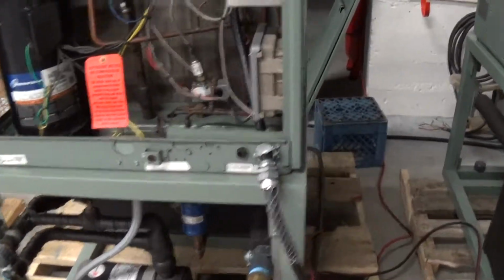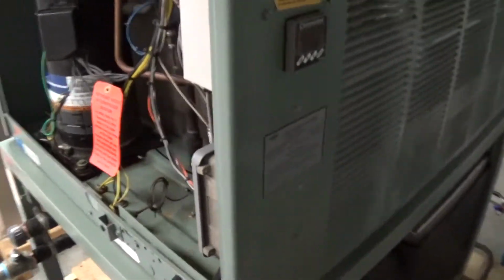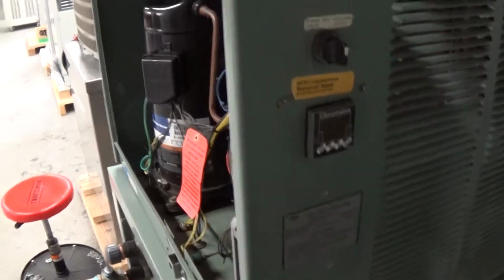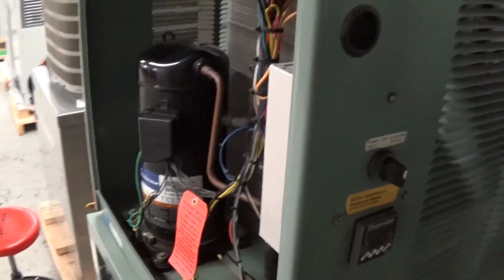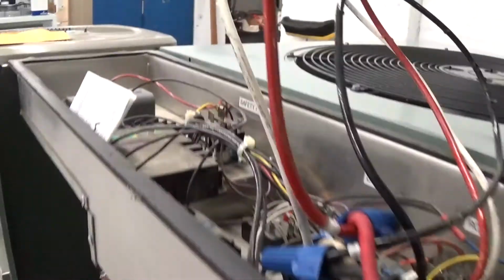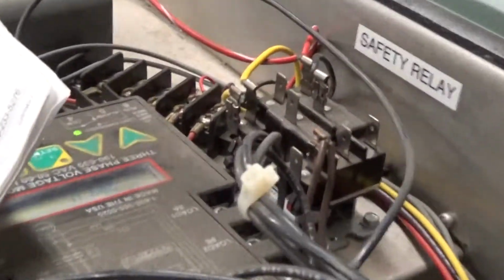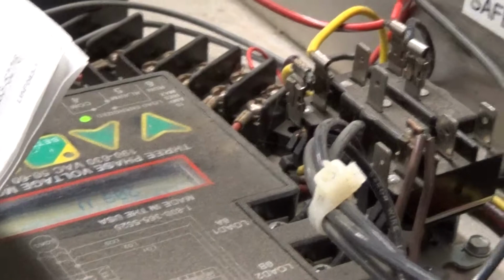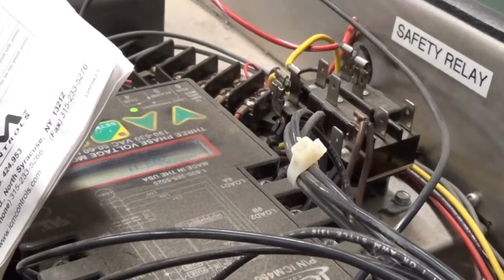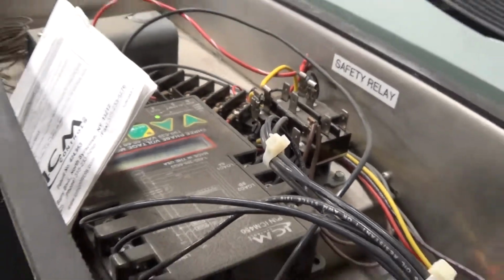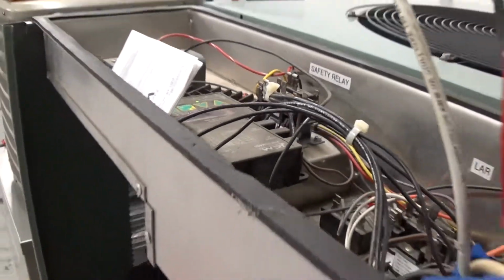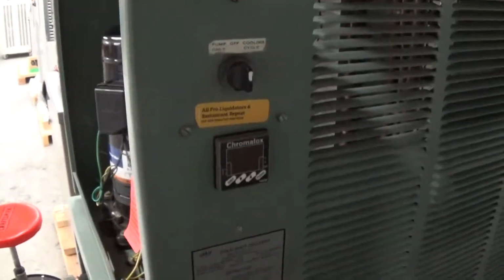When you first power up the unit at your main disconnect there on the top of the chiller, on the top of the chiller here you have that voltage monitor, that voltage regulator. It'll go into like a 5-minute delay countdown before it actually starts everything up. We've already done that by having power to the unit.